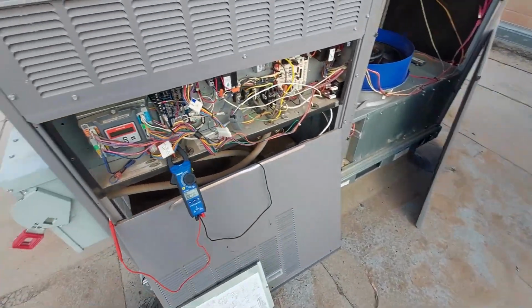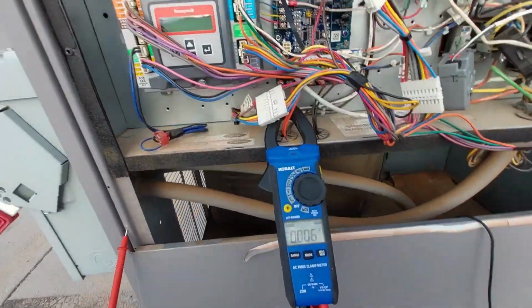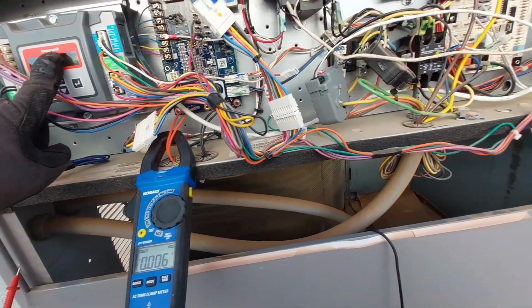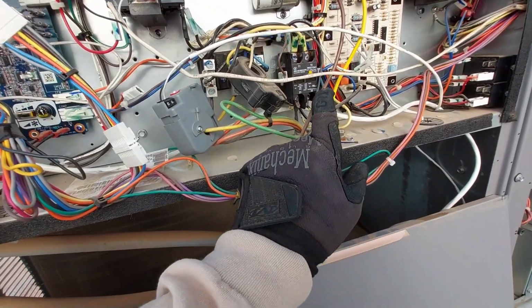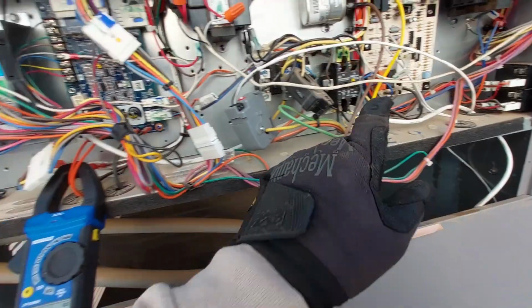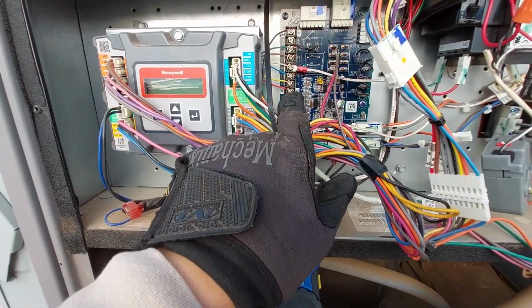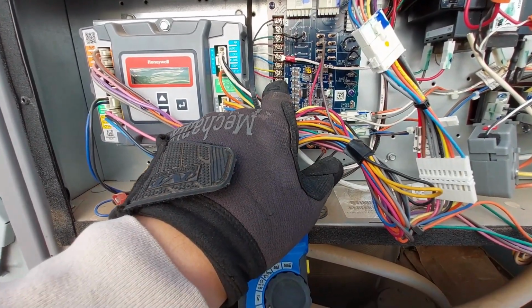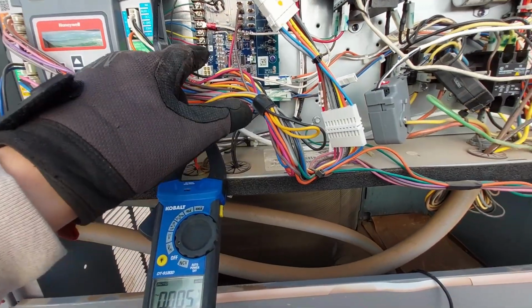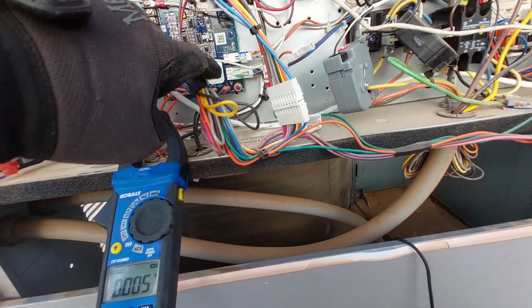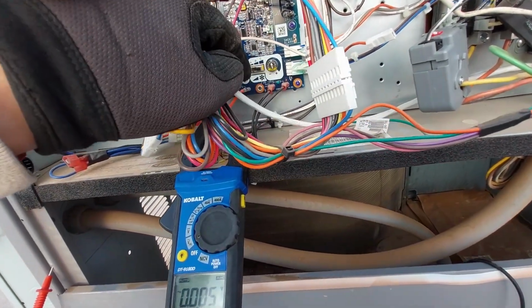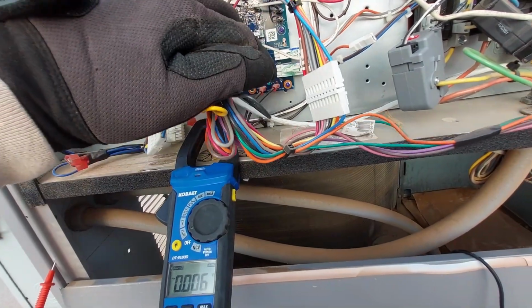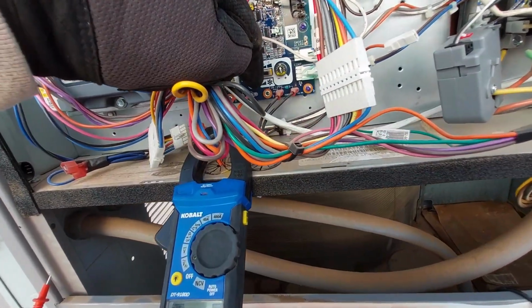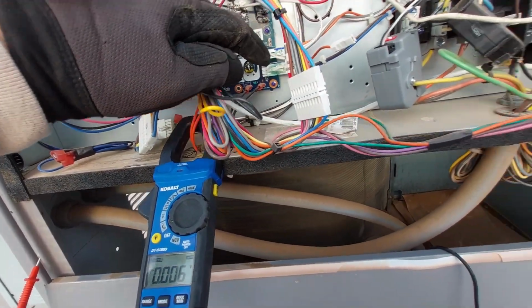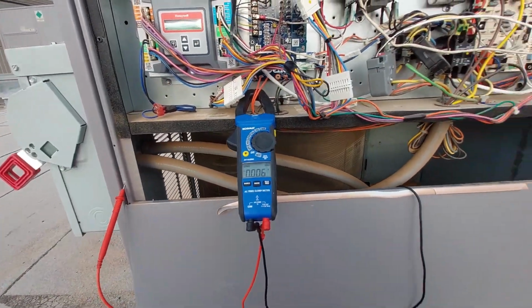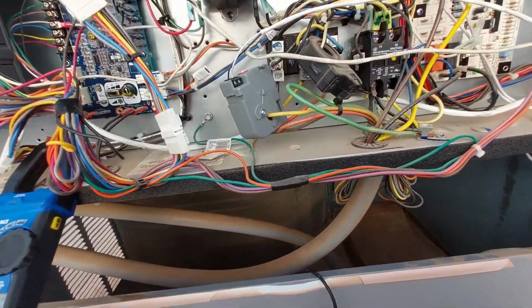Alright, so here's what's going on. This is still not working. Still not getting 24 volts. I'm losing it here. So I'm getting it at the Y1 for 24, and from there, I'm losing it. So I checked the low pressure switch, high pressure switch. I'm getting continuity through both of them on both sides. So that tells me we're good on refrigerant.